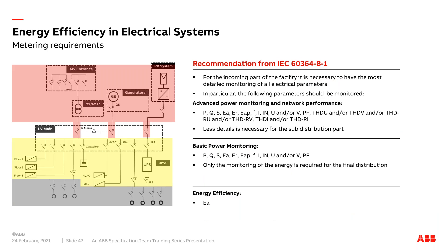In the future, we'd like to see everything in pink — able to monitor almost every outgoing circuit. When you look at the microgrid and decentralised energy scenario, it's crucial to have that in place to help command and control energy. Everything will be connected to the cloud as well. There are recommendations under IEC 60364-8-1 stipulating parameters to monitor at different levels: at main distribution, picking up almost every electrical parameter imaginable; at sub-distribution, basic power monitoring with a fair number of parameters; and at final distribution, monitoring active energy — kilowatt hours — and demand.